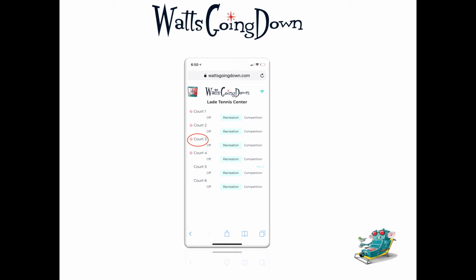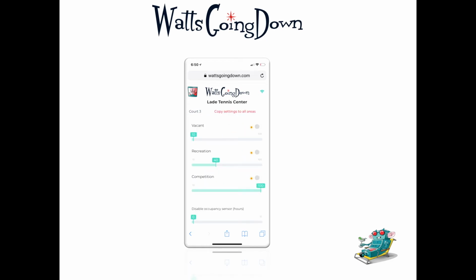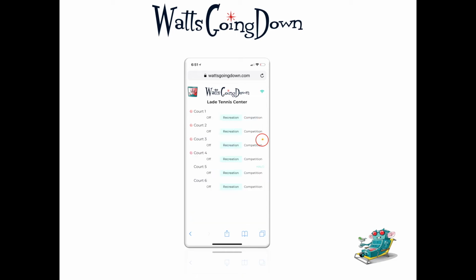So let's go back to our tennis court example, and let's turn on daylighting on court number 3 in recreation mode. So what we're going to do is go to court number 3. Now, standing on the court, you can just go through and move the slider until you get to a light level that you think is the light level that you want to maintain. In this case, it's going to be 75%. And now we're going to press the little slider there to enable daylighting, and we are done. That's simple. Now when we go back to our main home page, you notice that there's a little sun icon, and because court 3 is in recreation mode, the icon's telling us that we're actively using daylight harvesting.